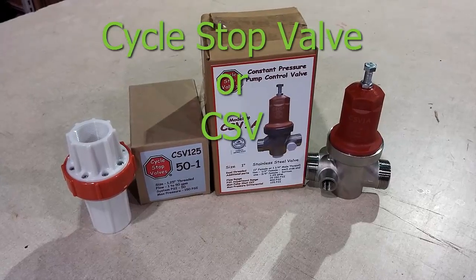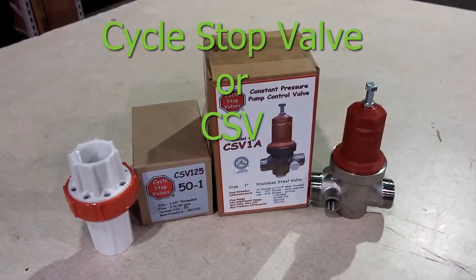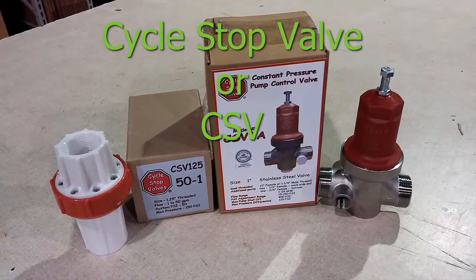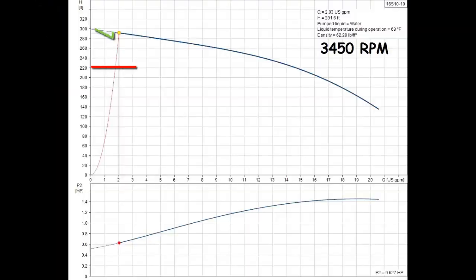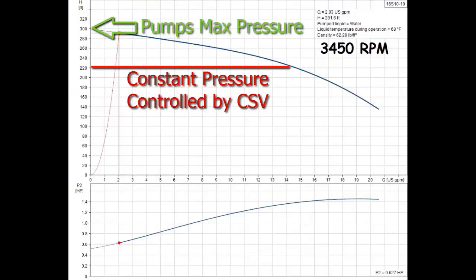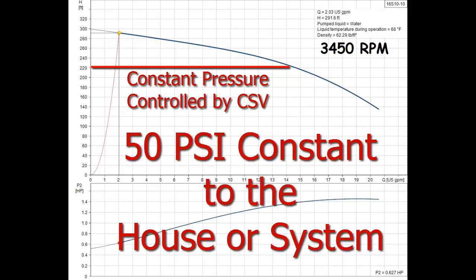Restricting the flow of a pump with a valve does not reduce the pump's pressure building ability like varying the speed does. The CSV reduces the pressure, so the house or system always sees a constant 50 PSI regardless of how much or how little flow is required.